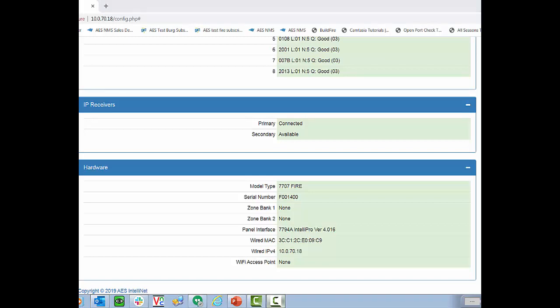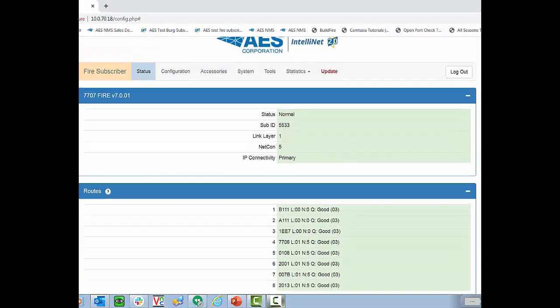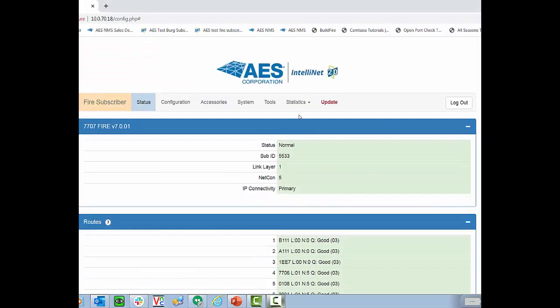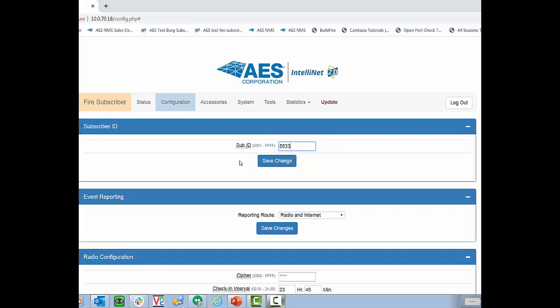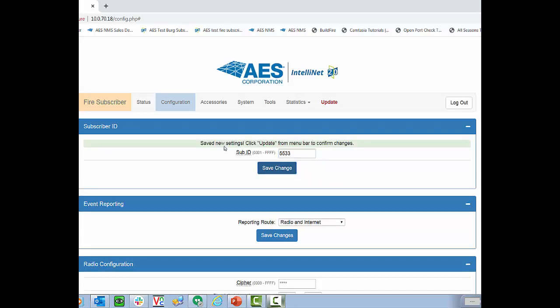All right, now that we've covered what's on the status screen, let's go up to configuration. And let me show you the two things that need to change with every installation. We'll select configuration. And then what we're going to do is we're going to change the sub-ID. So I'm going to go ahead and change it to 5533. This you want to match to the account ID of the FIRE panel. Hit select save changes, and it will say click update from the menu bar to confirm changes. If you're accessing this from your phone, you will have three little lines in the top right hand corner. Select the three little lines in the top right hand corner and then hit update. But we have one more change to make.